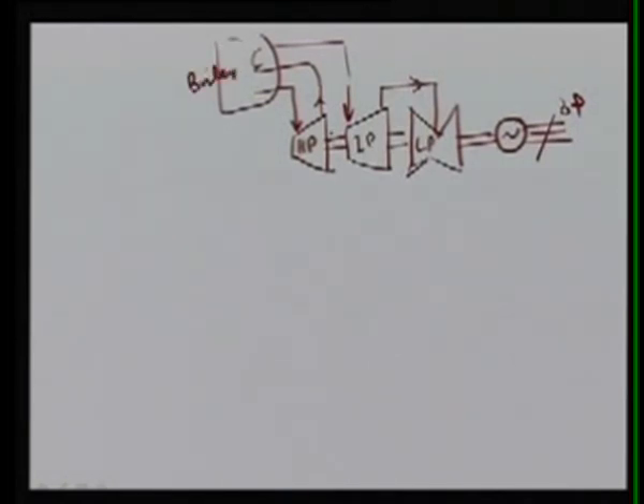So, we have here the shaft, and that is all: HP high pressure turbine, intermediate pressure turbine, low pressure turbines, all on the same shaft where your alternator, the synchronous machine, is connected. So we have here 4 rotating masses, all connected with the shaft, and that shaft has some stiffness constant, it is not infinite.